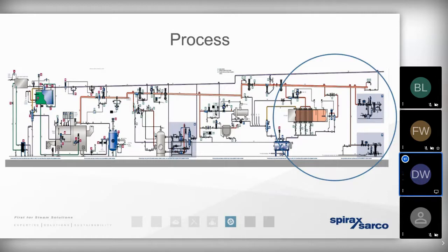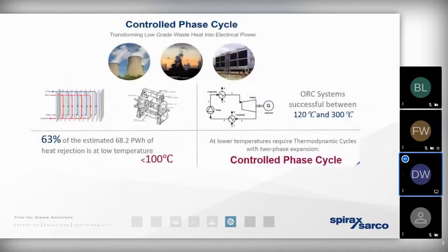We know that a lot of sites that are utilizing thermal energy may not use steam. They may utilize thermal energy from other sources. They may not have steam on site, but they may still have a significant amount of waste heat energy that's put to waste in the form of effluent. And we know that a lot of these industrial processes can reject a significant amount of waste heat. And this is often going to be at temperatures that are relatively low, lower than most traditional methods of heat recovery can make use of.